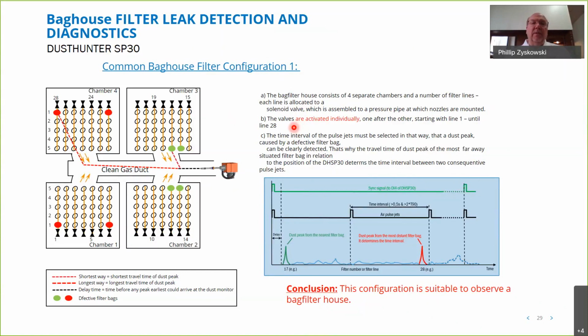So the key here is that the valves are individually activated. So that's represented here in these different chambers. And so knowing which valve is activated at the time, with that built-in delay time we showed you earlier, the Dust Hunter SP will determine which bag in this row had an issue with breakthrough. And you can see that indicated here, a large peak that occurred at that particular time. So it's really a timing sequence, knowing where the cleaning was being done at the time the Dust Hunter saw an excursion.